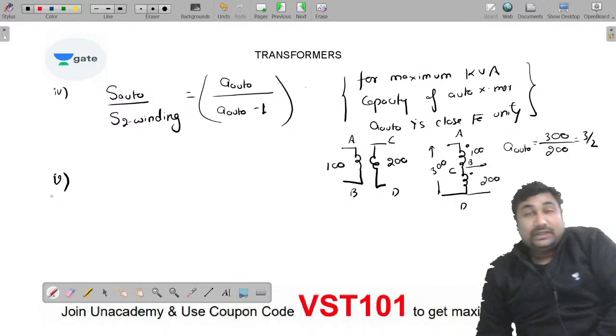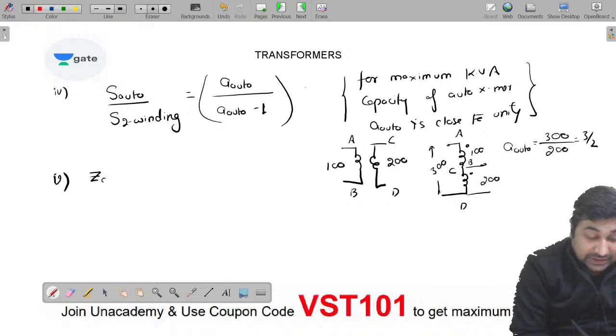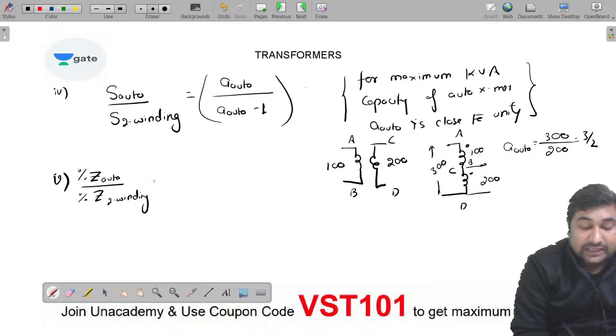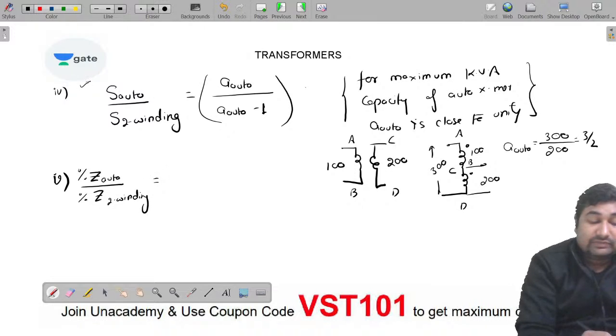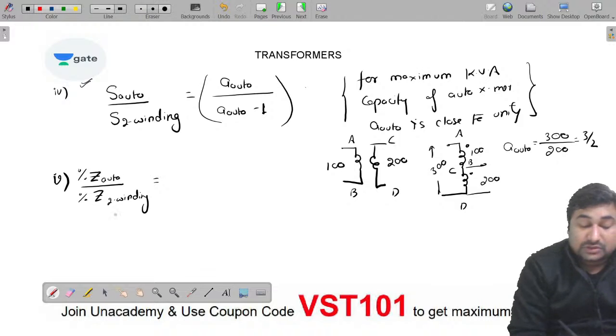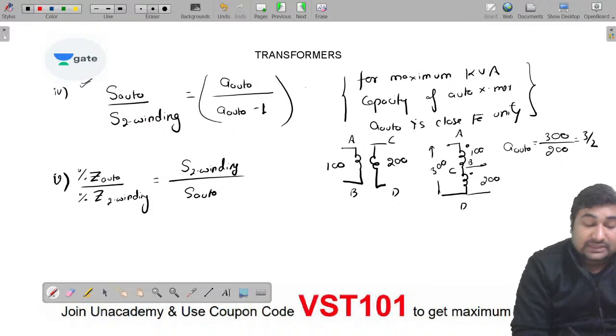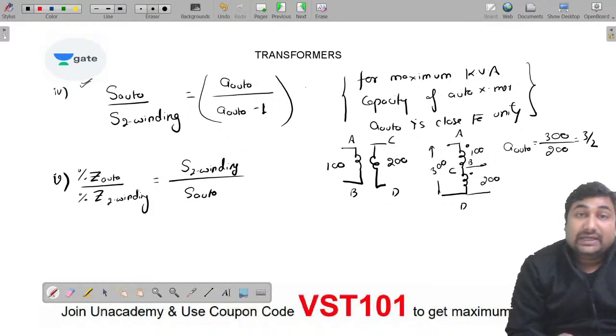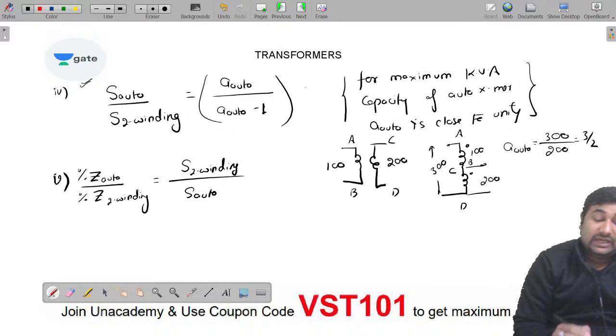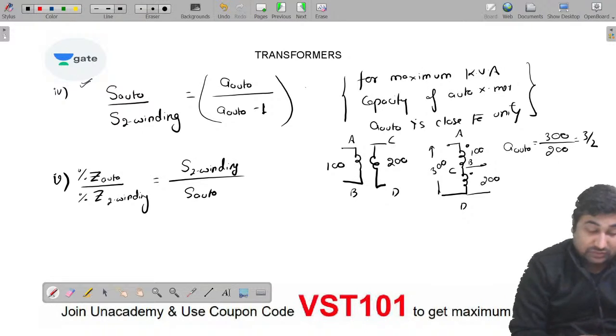Very important. Now please see, you have to remember about the percentage impedance of auto transformer to percentage impedance of two winding transformer. Whenever we are connecting a two winding transformer as an auto transformer, we can go by the first one, kVA capacity. Second one, you can also go by the percentage impedance. So for percentage impedance of auto transformer to two winding transformer, you can write, sir, kVA capacity of two winding to kVA capacity of auto transformer. Always remember the percentage impedance of auto transformer decreases compared to the two winding transformer, whenever we are connecting a two winding transformer as an auto transformer.